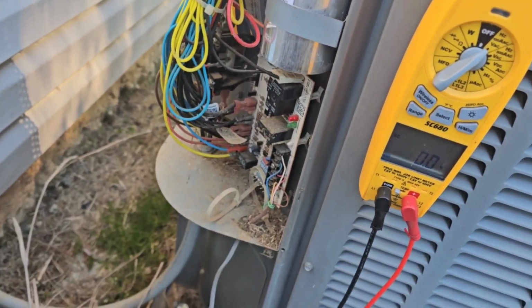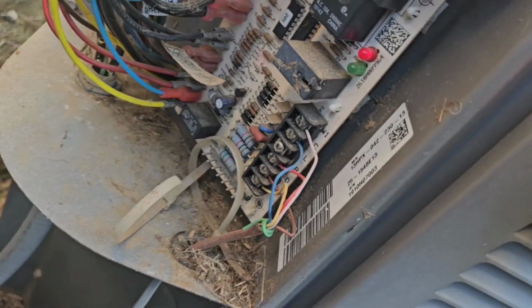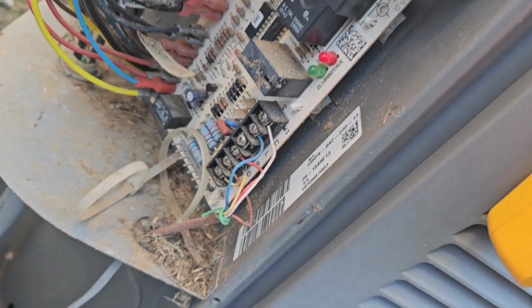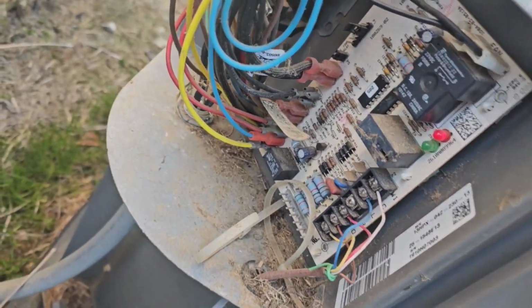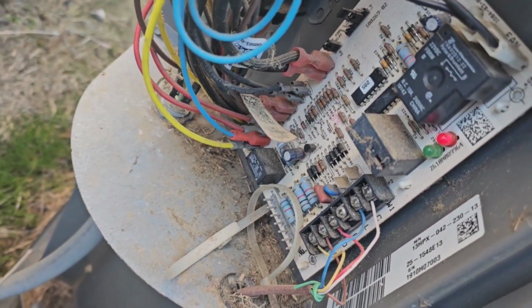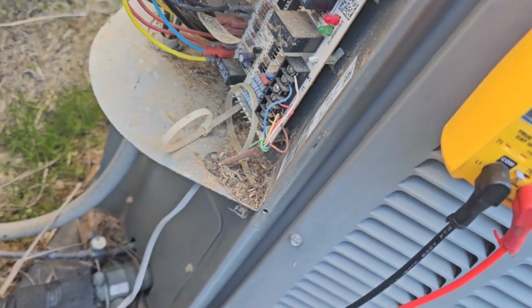So what this tells me is that from the Y on the board, from the thermostat bundle to the Y1 coming out, there's an issue with the board.